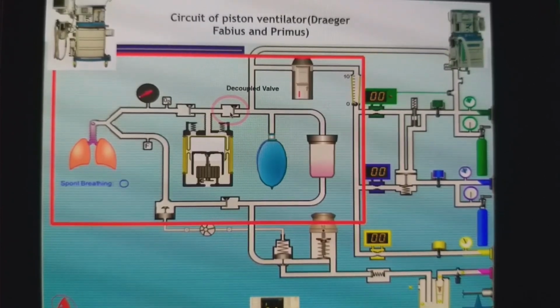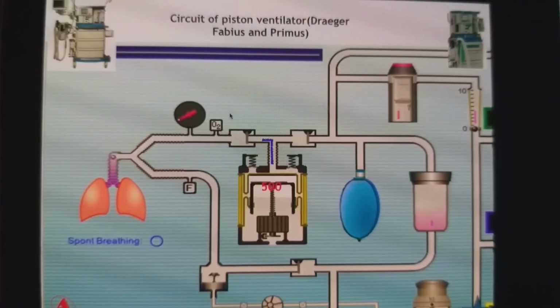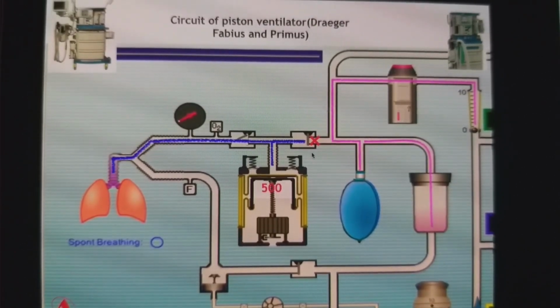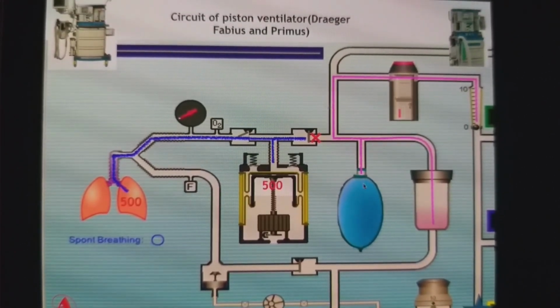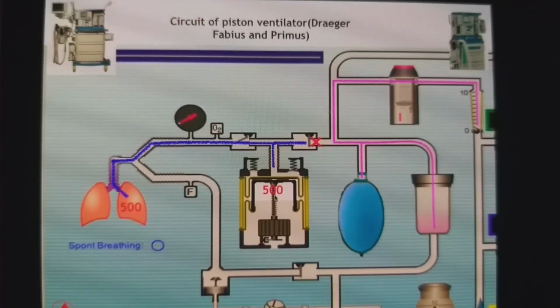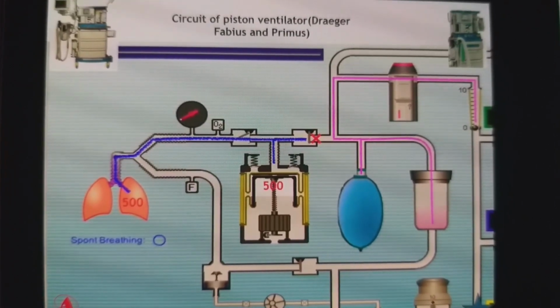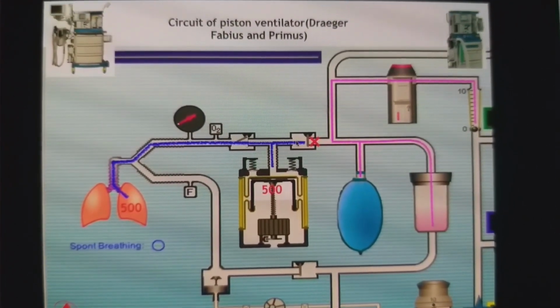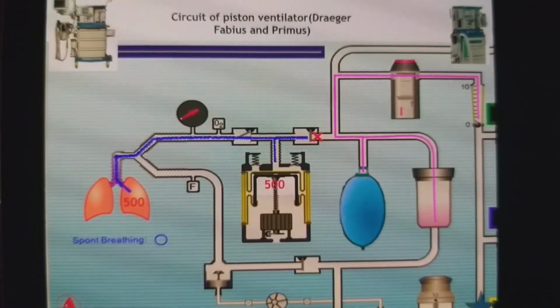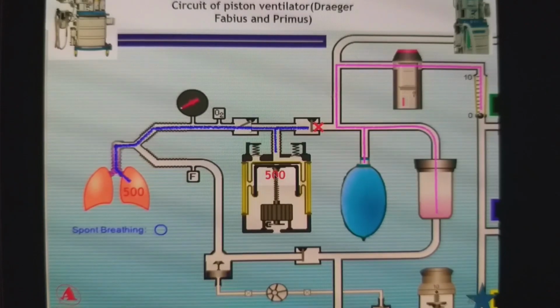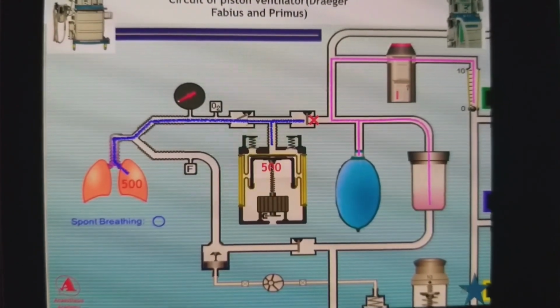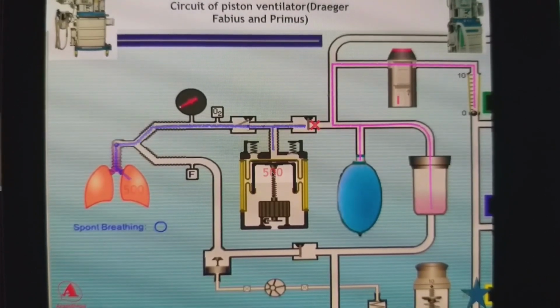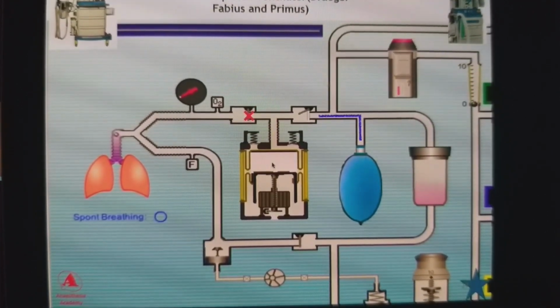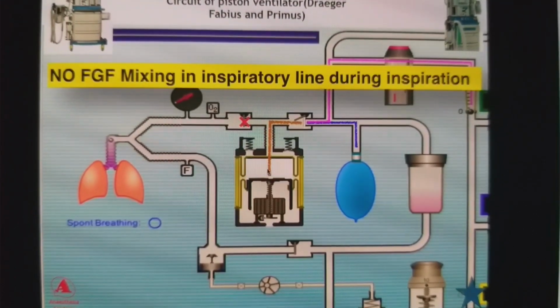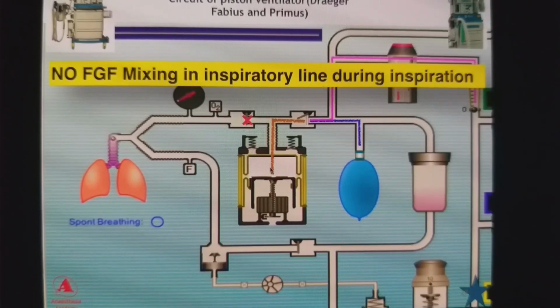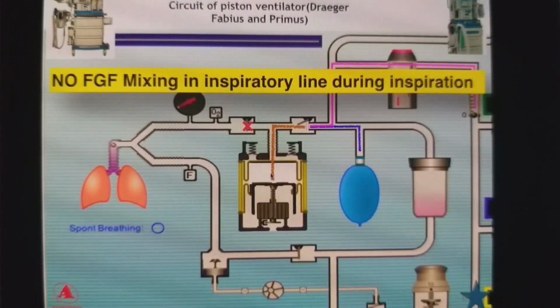So when the piston is trying to deliver a 500 ml tidal volume, this decoupling valve will get closed. So you don't get any fresh gas flow or any flow from the reservoir into the inspiratory line. Because of this decoupling valve, fresh gas flow is not mixing in the inspiratory line. So whatever is delivered by the ventilator goes straight to the patient. If you decide to deliver 500, it will only deliver 500. It will not be affected by fresh gas flow changes. Of course, in expiration, when the piston pulls out, the reservoir gas as well as fresh gas flow will go into the piston. So there is no FGF mixing in the inspiratory line during inspiration.